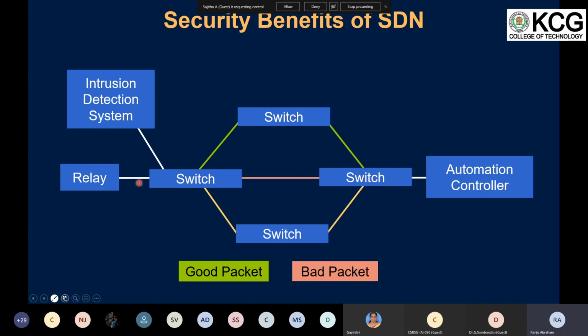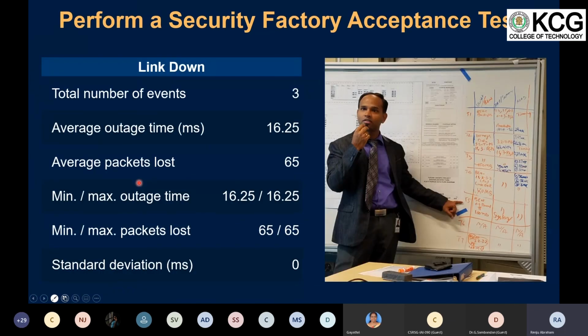For security, apart from the usual factory acceptance test which we do for the system or solution we provide to our end user, a communication or cybersecurity factory acceptance test should also be done. It should be made a standard practice by all the vendors or manufacturers. In case the network links go down, what could be the impact, the outage time, how many packets are lost, and other features can be measured in that factory acceptance test.